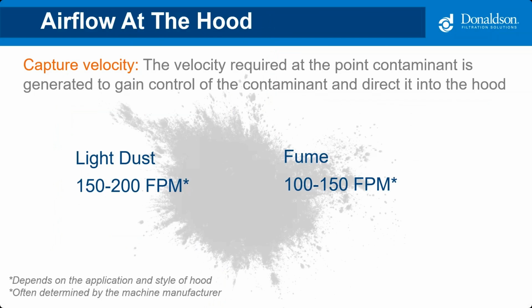When determining the required airflow at the hood, the main design factor is called capture velocity. And this is the velocity that's required at the point where contaminant is generated to gain control of that contaminant and direct it into the hood. The main goal here is to keep the operator safe and keep the particulate away from their breathing zone. Capture velocities range from 150 to 200 feet per minute for light dust and 100 to 150 feet per minute for fumes. Both of these are prevalent in battery manufacturing, but just know that the capture velocity is often determined by the machine manufacturer and no additional hooding may be required.